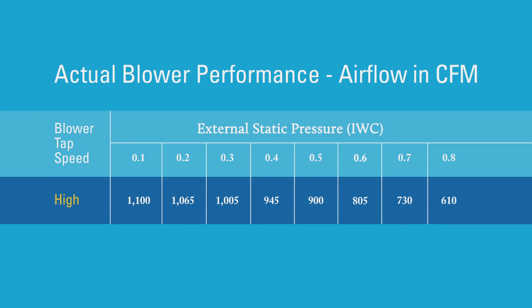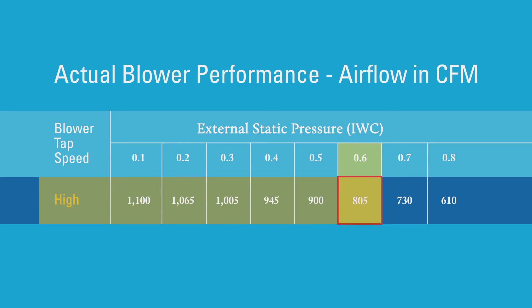Here we see the actual blower table for the furnace and air conditioner that James has installed. Using our fan speed setting and the total external static pressure, we look up our HVAC fan airflow. Not too difficult, right?